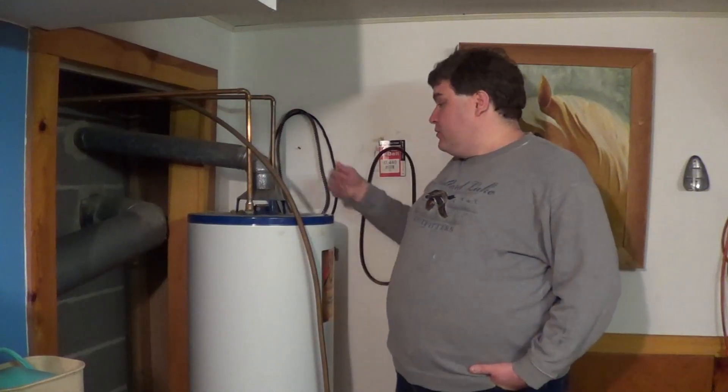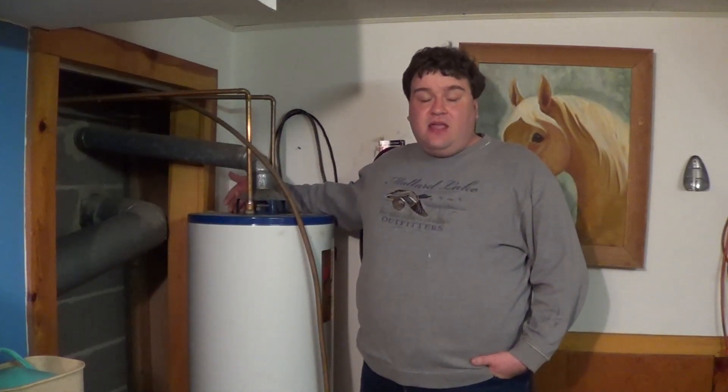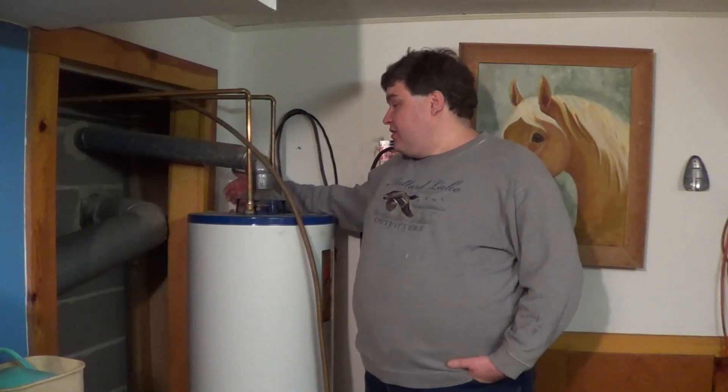That's the kind of thing I absolutely don't understand. Now this water heater definitely has a sacrificial anode rod in it as well. However, I have no reason to believe it's ever been replaced — the threads on it look to be untouched, as does the head of the fastener that holds it in. Likewise, there is a tuft of insulation around it that appears to have never been disturbed. So my question is: is it a matter of reduced quality being employed in the manufacture of new water heaters, or is there some other reason why they don't seem to last as long as they used to?